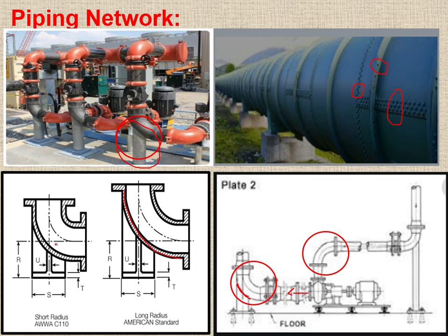If there is a short radius, that means there will be a more pressure drop, and there will be a stronger force on the elbow. So in that case, we have strong anchoring supports. Okay.